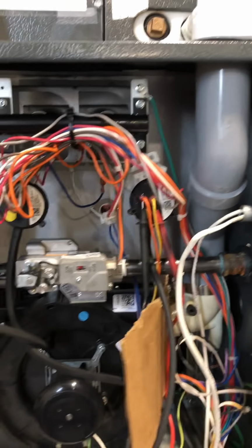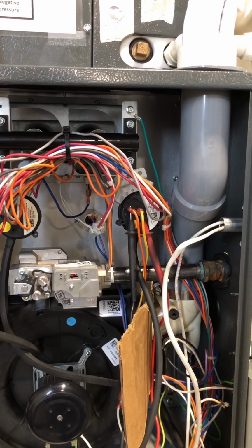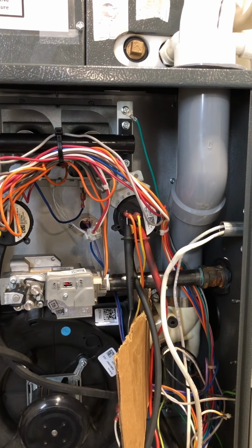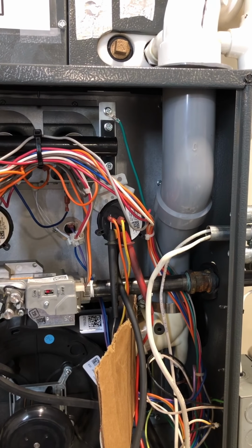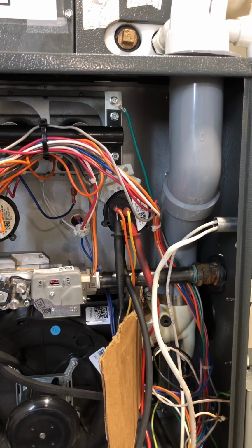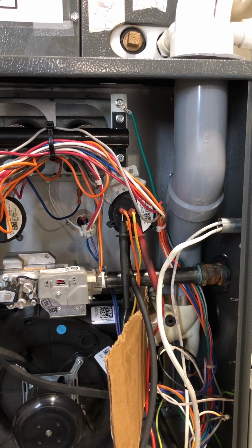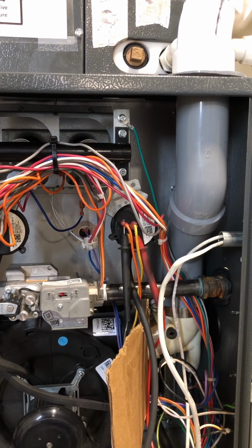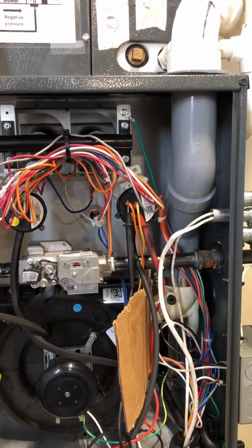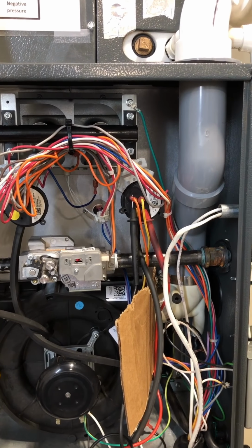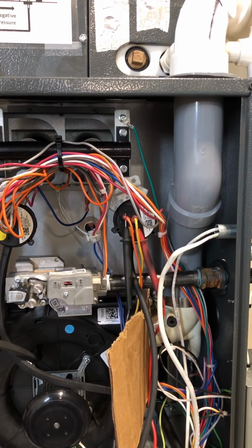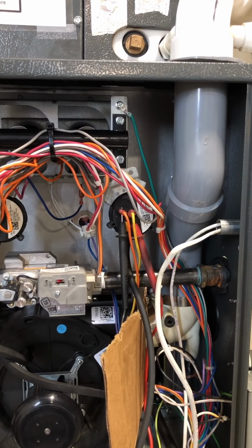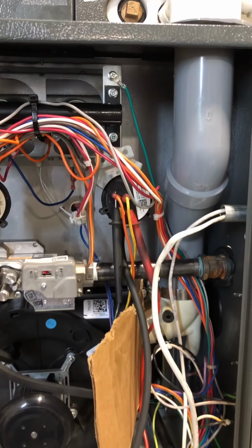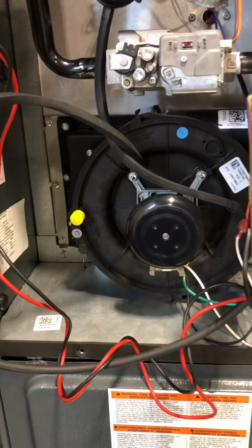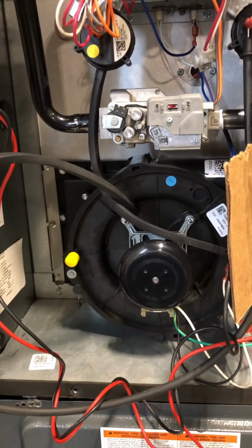Okay. Number two, as soon as we get a call for heat, the board inside this cabinet here is going to send 24 volts through the safety circuit, which includes this pressure switch. And that pressure switch needs to be open. If it is not open, nothing will happen past that. It needs to be open to start. As soon as it proves that it's open, this inducer motor will start up and start pulling a negative pressure on that heat exchanger.